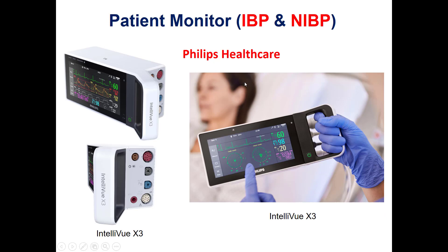Another patient monitor manufactured by Philips is the portable X3. The patient monitor has many parameters and corresponding connectors — one for temperature, one for invasive blood pressure, one for CO2, one for pulse oximeter, one for ECG or electrocardiogram, and one for non-invasive blood pressure.